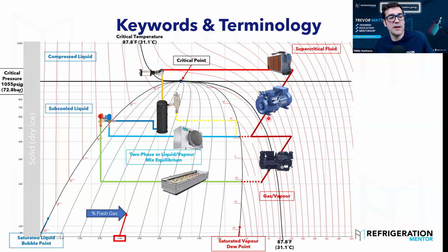That's why there are designers designing systems, especially in our design program. I've seen designers winning projects now by changing up the way they do their design. So maybe when they're doing a design, they're adding a plate heat exchanger on the drop leg to get actual liquid getting to this valve, or adiabatic cooling, or parallel compression.